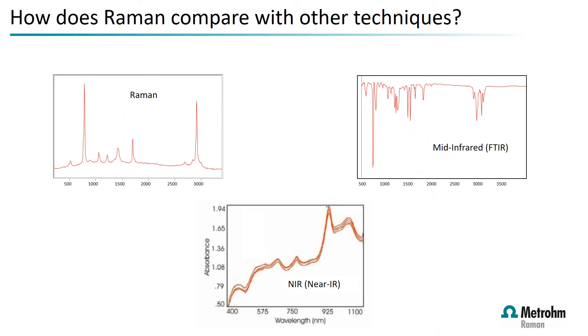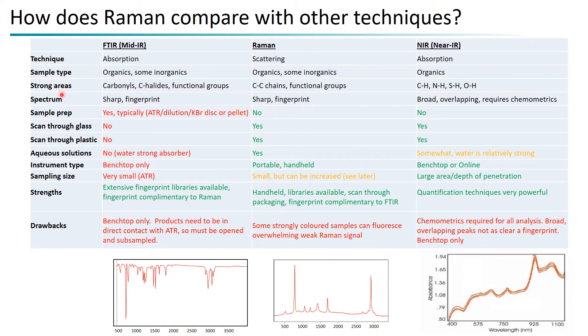How does Raman compare with other techniques for identification? Comparing Raman versus near-infrared and mid-infrared (FTIR): both FTIR and Raman have very sharp fingerprint-type structures for their chemical libraries. FTIR is extremely strong for polar molecules — carbonyl groups, halides, carbonyl bonds — while Raman is extremely sensitive for non-polar molecules such as organic carbon-to-carbon chains and functional groups.